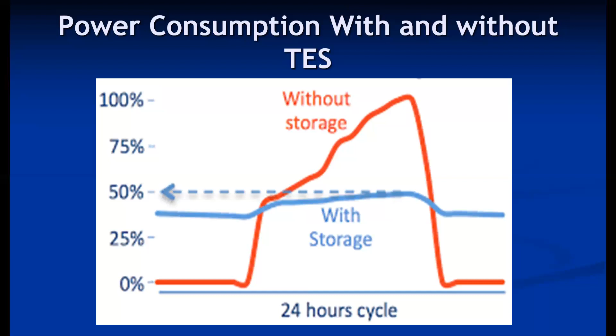Another advantage we can realize: without storage, you have to continuously monitor and regulate the capacity of the system. So a better capacity control modulation technique should be used. We already discussed capacity control in the second unit, that is compressor capacity modulation. There is a cost difference of almost 1.5 times between a compressor provided with capacity modulation and one without. So 1.5 times to almost double the cost is what the purchaser needs to bear if they have to purchase the compressor with capacity modulation. But with the help of a thermal storage system, we can purchase a compressor without any capacity modulation, because the compressor runs with almost uniform capacity. So no complicated capacity modulation mechanism is required for the compressor, and ultimately the compressor cost is reduced substantially. So these are the two major benefits of thermal energy storage, meaning the system along with the thermal storage device.